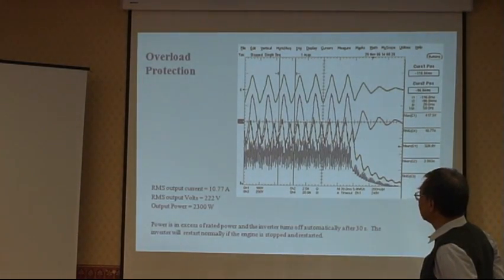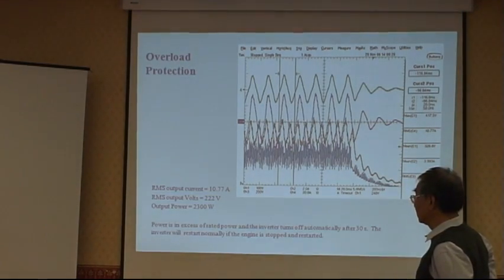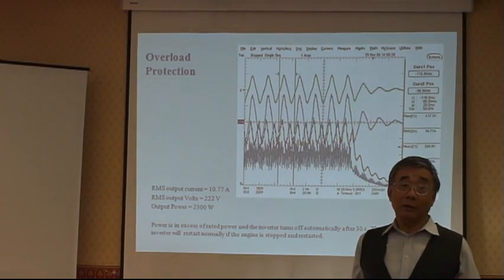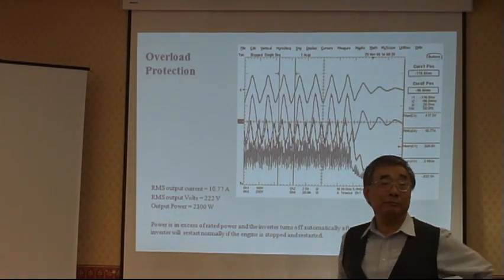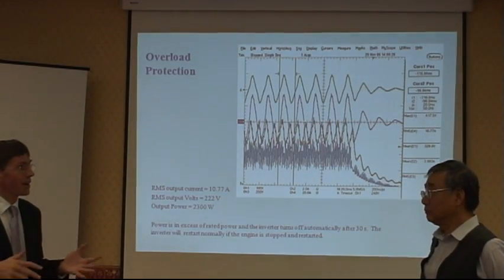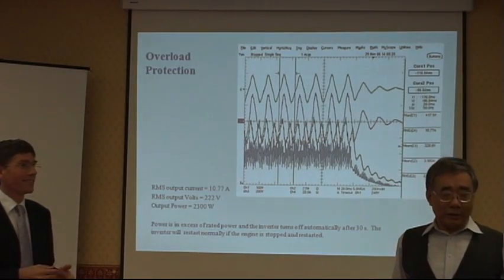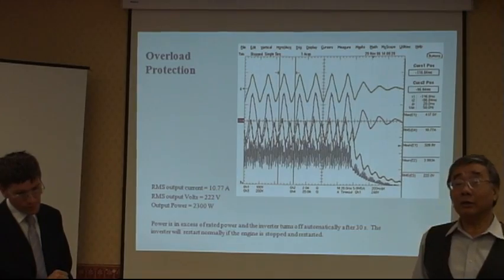For the overload, we can go to 50% overload if you need to start electric motor. So on the generator, if you want to start a large induction machine, a compressor, then as the machine accelerates, it draws a lot of power. 发电机用在感应机的话，感应机启动电流很大，对发电机来讲是过载状态，它可以过载150%，也就是多50%。But if the power remains at high power, then the generator shuts down after 30 seconds. Yes, but it's maybe damage to the engine. Yes. Not generator.